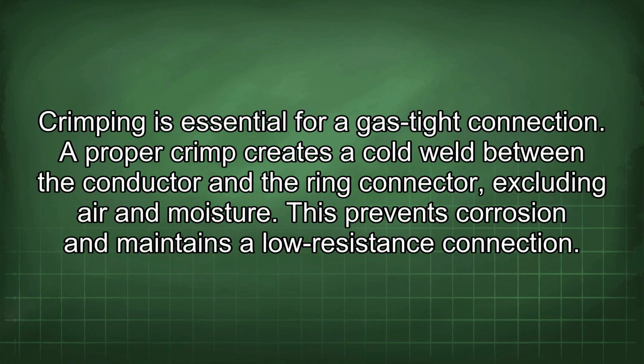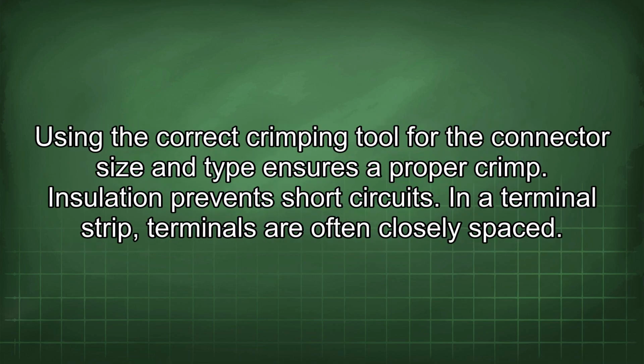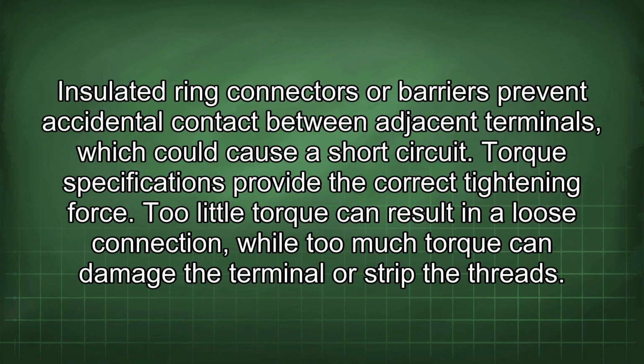Crimping is essential for a gas-tight connection. A proper crimp creates a cold weld between the conductor and the ring connector, excluding air and moisture. This prevents corrosion and maintains a low-resistance connection. Using the correct crimping tool for the connector size and type ensures a proper crimp. Insulation prevents short circuits. In a terminal strip, terminals are often closely spaced. Insulated ring connectors or barriers prevent accidental contact between adjacent terminals, which could cause a short circuit.